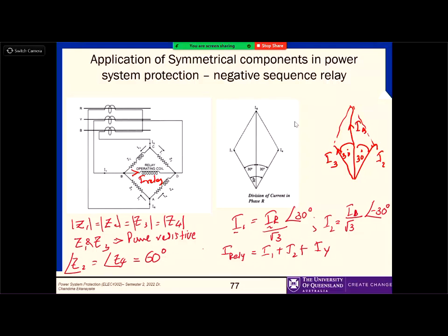And therefore, is the increase in temperature an immediate action, or does it happen later? Let's say when the negative sequence current is present in the system, is the temperature increase immediate or does it happen with a time lag? There's a time lag, because the temperature won't increase suddenly. But if you detect these negative sequence currents in the system, you can take appropriate actions before the temperature increases. That's why you need to measure negative sequence currents related to the generators.